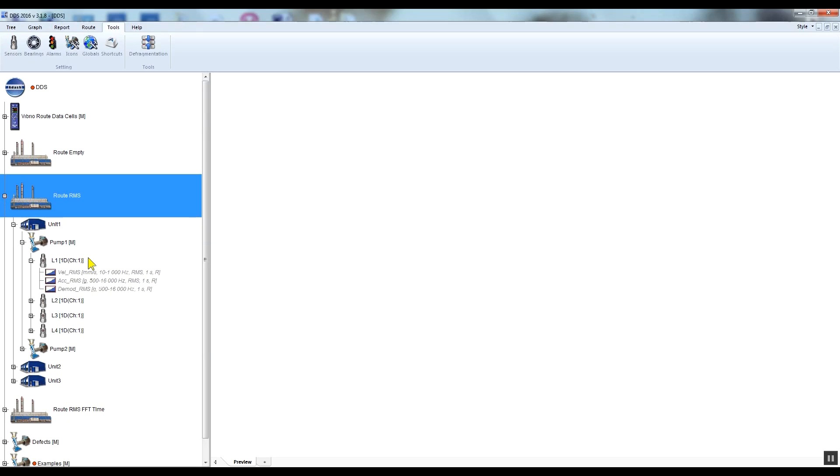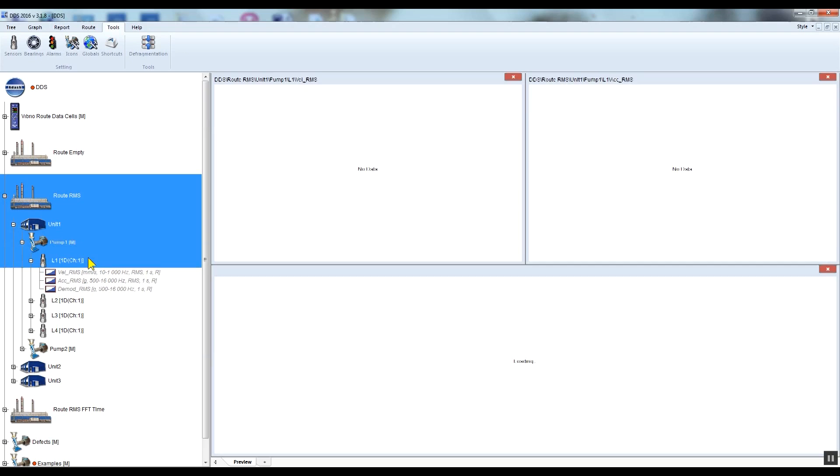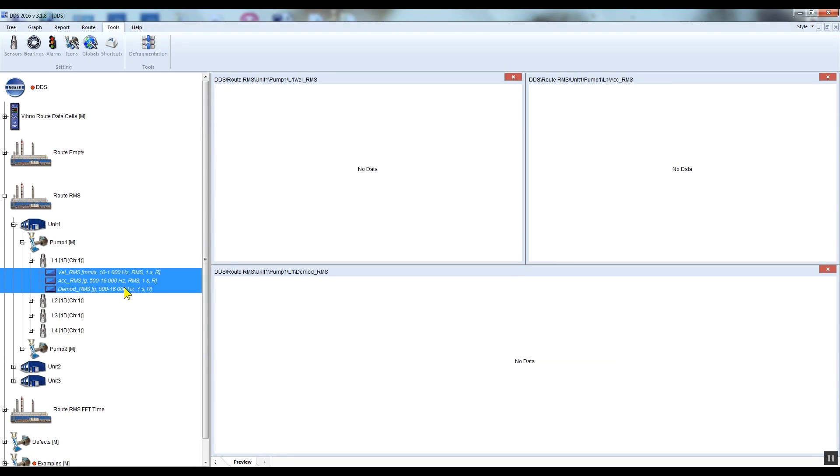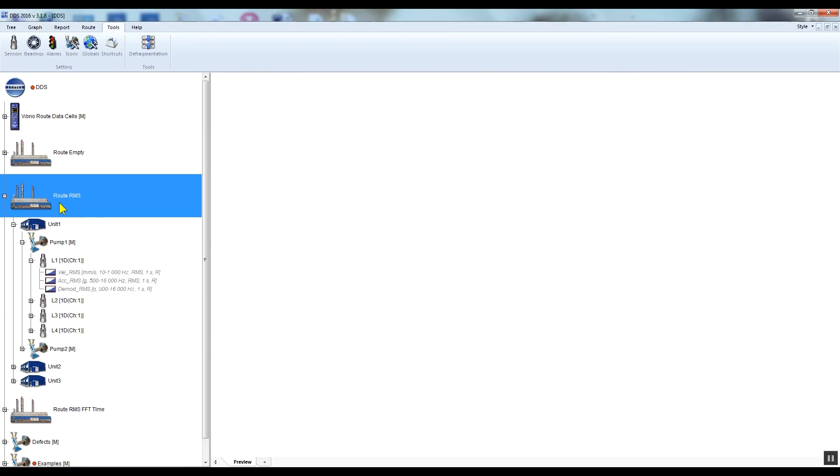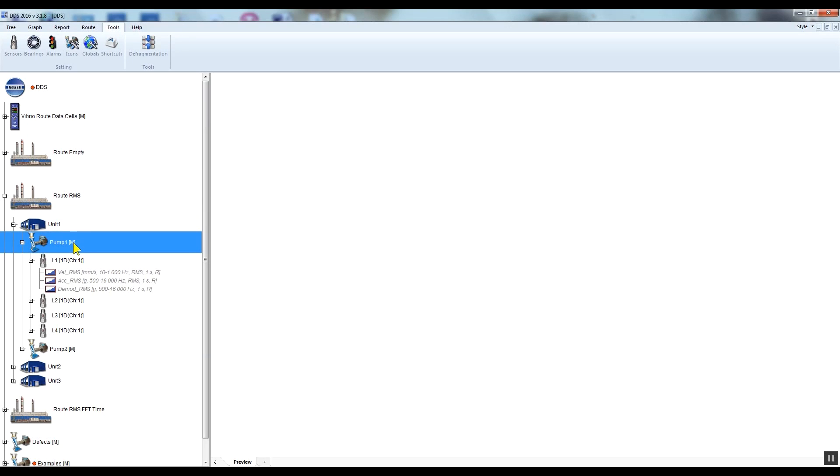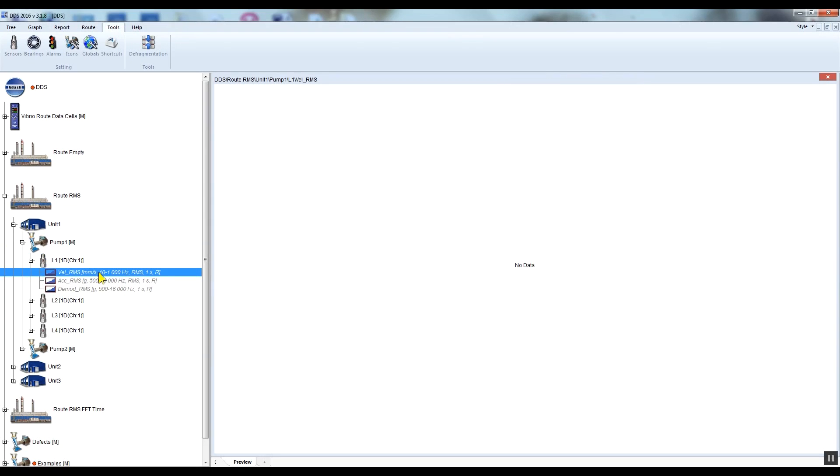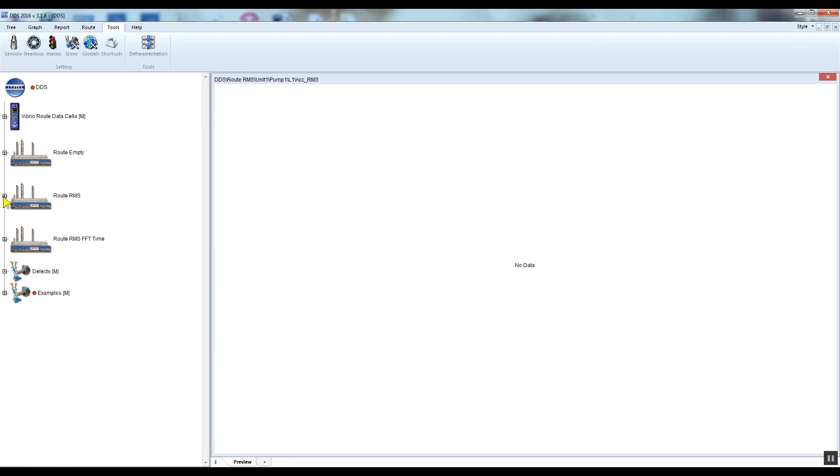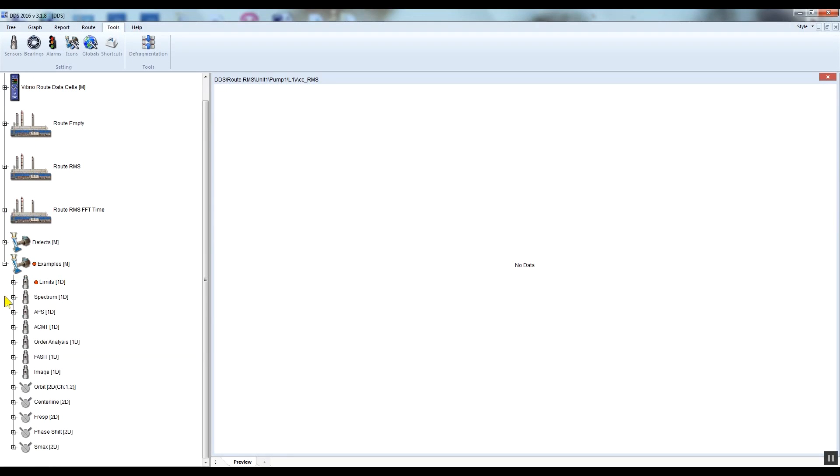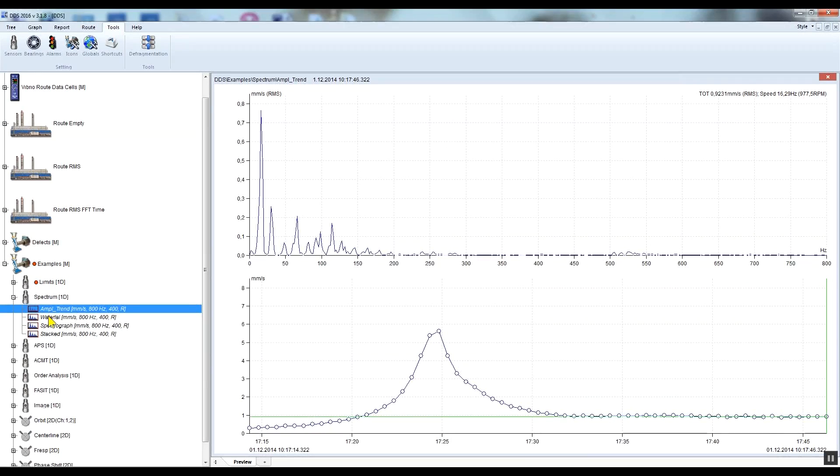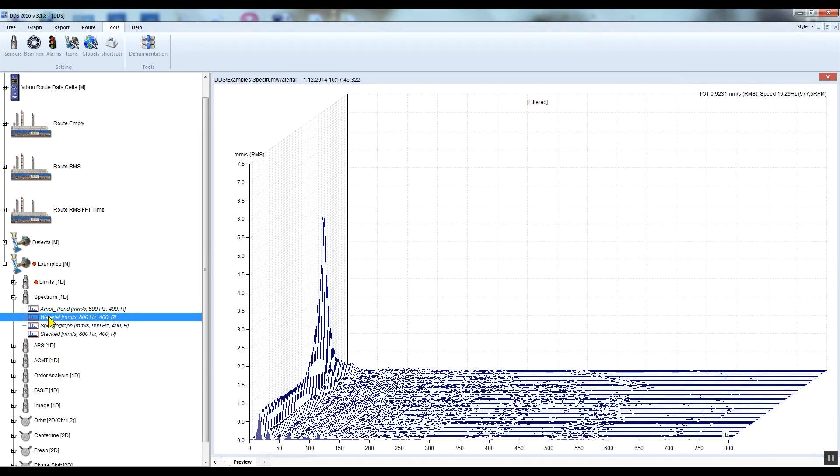Let me explain two basic terms which we will use before we create our own tree: tree items and data cells. Tree item is part of the tree and does not contain measurements. A tree item can be, for example, a whole factory, an individual machine, or a measurement point on the machine. Another type is data cell. A data cell contains measurement settings, for example overalls, spectra, or time waveforms. Typically the data cells are created under the measurement point.